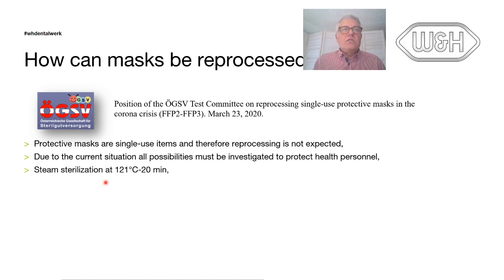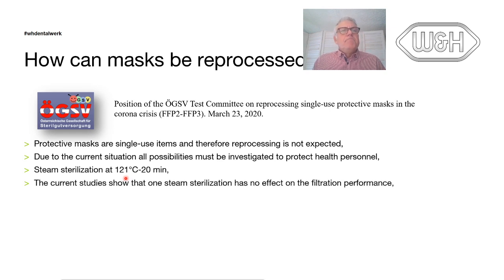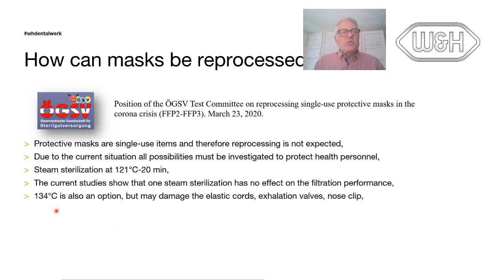Steam sterilization at 121 degrees Celsius, 20 minutes. For the US, it's 250 Fahrenheit. They processed once and had not seen any negative effect on the filtration performance. They also tried a higher temperature, which is slightly faster and also an option, but then you can see some damage on the elastic cords, the exhalation valves and the nose clips.